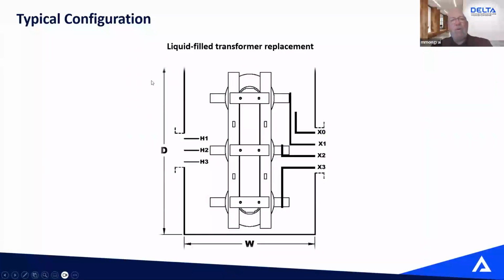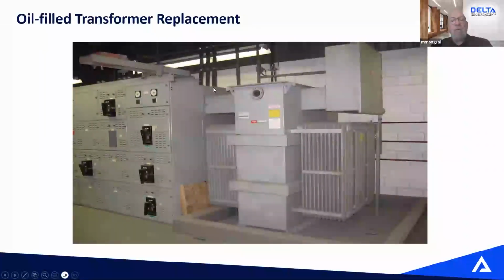When we deal with liquid-filled transformer replacement, usually a liquid-filled transformer is going to be much more compact in footprint compared to a three-phase dry-type transformer. And usually what we need to do in those cases, when you keep your existing equipment, we just turn the core and coil 90 degrees. So instead of having a left to right orientation, looking from front, we have a front to back orientation. And we put flanges or throats on the side of the enclosure to connect to the existing equipment.